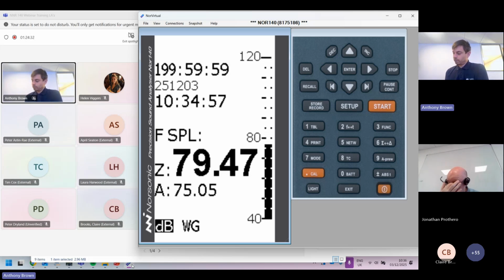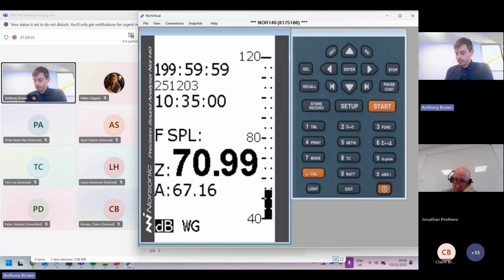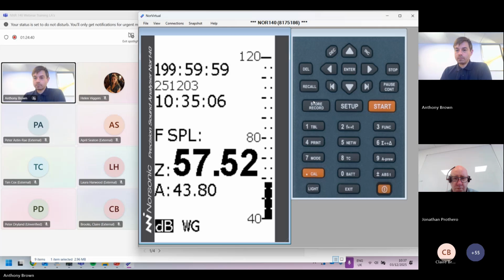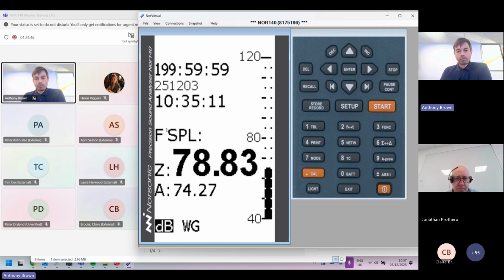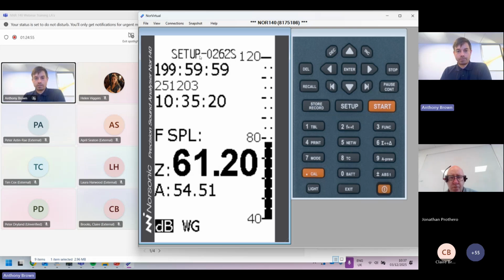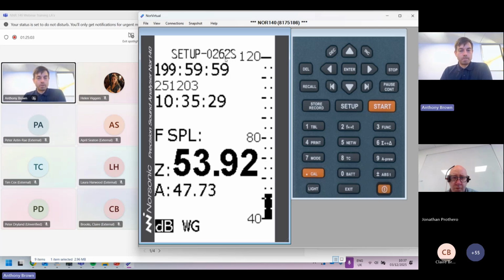So to do that, to save those settings, you would need to press a button called the store record key, which is next to the setup key. So you make sure that you're on this home screen once you've done all your setting changes, and then you press the store record key, and then it creates a setup file, which in my case is 262. And you just note that down on your notepad or put it in your box. And the next time you want to load in the settings that we applied today, you would press the recall key to do that.